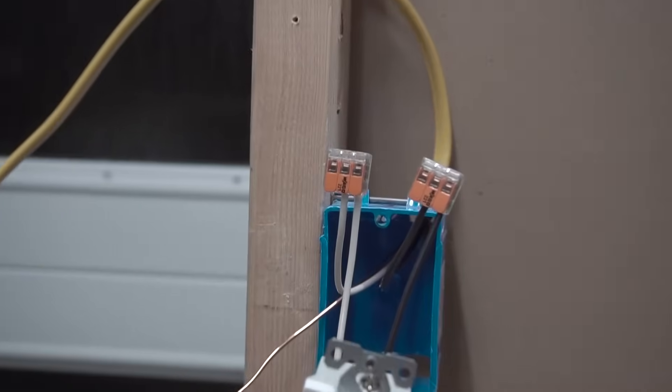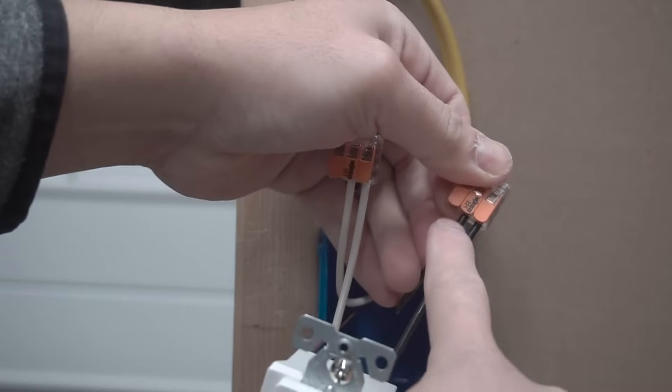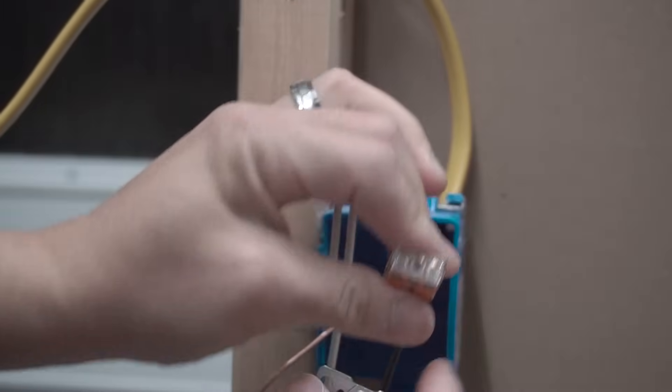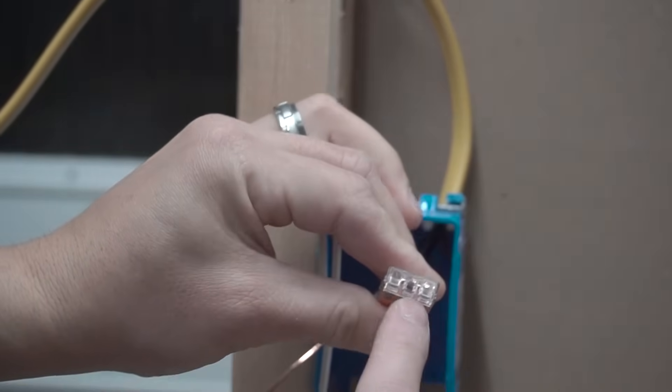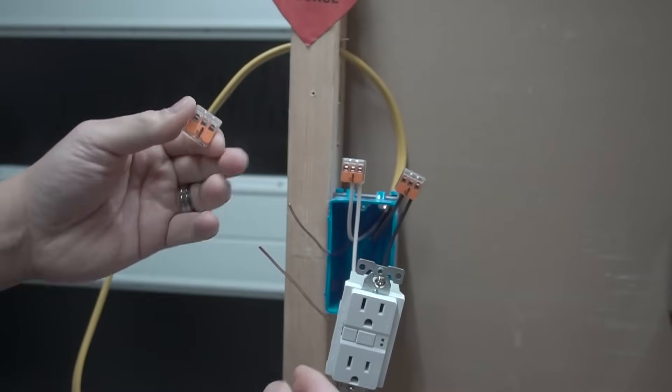Now another key thing that I want to show you is make sure that when you're wiring this there is no exposed copper onto the WAGOs and make sure that on the top ceiling of the WAGOs, you can see that it is touching up there of the wire.